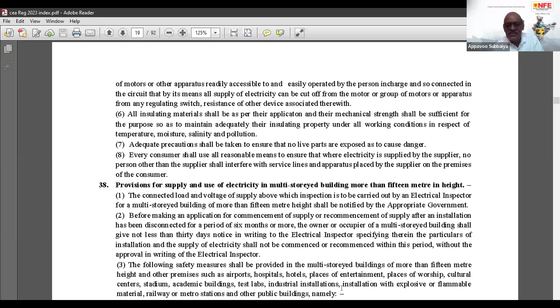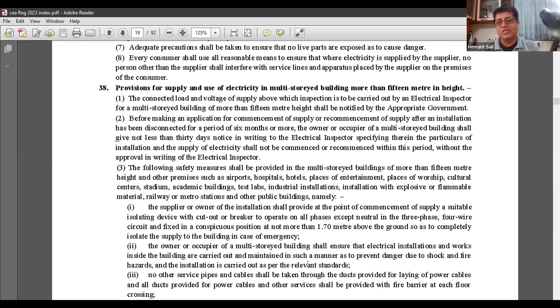See, this doesn't actually come under the purview of consumers. The point of supply is the incoming terminal of the switchgear provided by the consumer, so till that point it is the responsibility of the supply company to provide supply. With this regulation, the use of cables within the electrical shaft, the vertical shaft, has been prohibited nowadays for buildings above 15 meters.